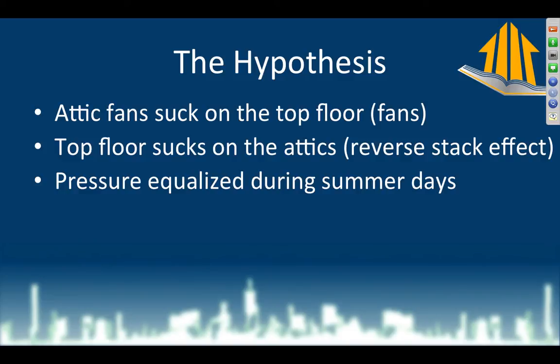It's about 4 pascals, like I told you, in the attics, depressurized, and due to the delta T today, it was about 1.5 pascals per floor, so that's 2 floors. That's about 3, so they're kind of sucking on each other in equal measure.